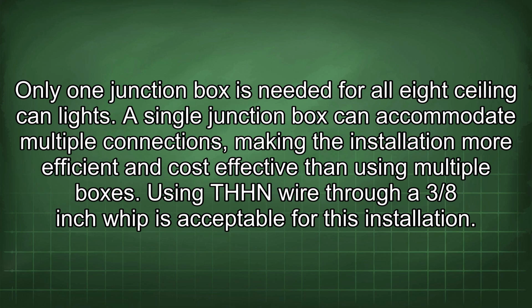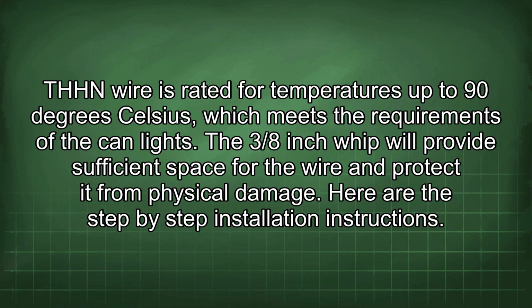A single junction box can accommodate multiple connections, making the installation more efficient and cost-effective than using multiple boxes. Using THHN wire through a 3/8" whip is acceptable for this installation. THHN wire is rated for temperatures up to 90 degrees Celsius, which meets the requirements of the CAN lights. The 3/8" whip will provide sufficient space for the wire and protect it from physical damage.